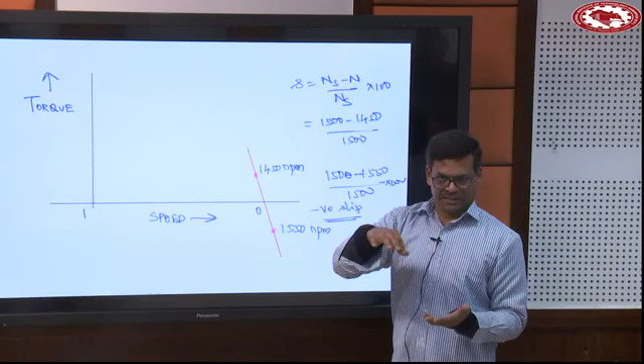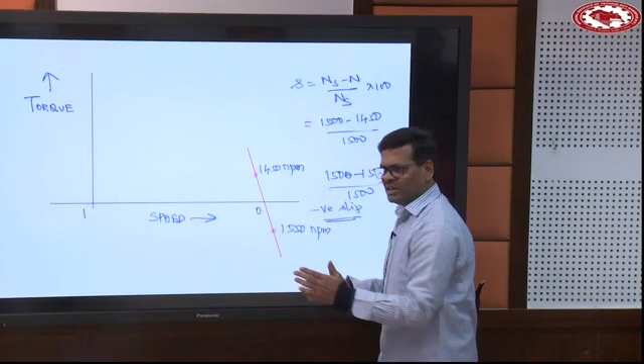Although you can keep on loading the shaft, the windings will be carrying 5 ampere, 6 ampere, 7 ampere, but it is designed for 5 ampere. If you are injecting more current for a longer duration, the insulation over the winding will be stressed and there will be damage. So you should not do it. All right. So the speed range is just 50 rpm, 1490 to 1450, 40 rpm. The same way it is applicable here also, only 50 rpm.